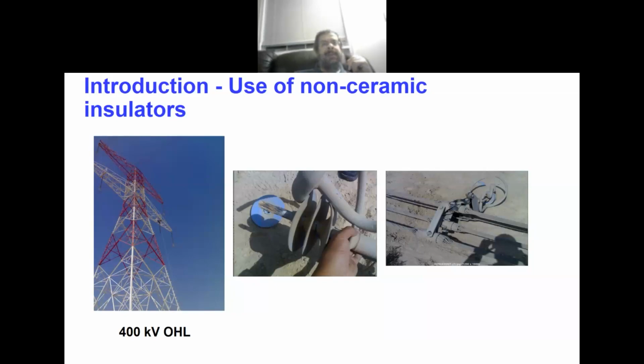This is an example from one of the Gulf countries using polymer insulators. Unfortunately, this is a case of severe aging in the weathershed material of the silicone rubber. Once these materials start to age and erode, the fiberglass core becomes exposed to environmental conditions. The fiberglass core is not well protected against these conditions, so damage occurs, and eventually the fiberglass suffers what we call brittle fracture. They fracture, and the whole 400 kV line falls to the ground - which is extremely bad, as you can imagine.